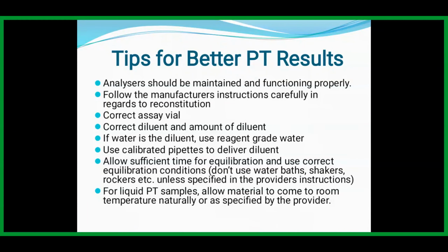If water is the diluent, use reagent grade water. Use calibrated pipettes to deliver diluents, very important. Allow sufficient time for equilibration and use the correct equilibration conditions. Don't use water baths, shakers, rockers, etc., unless specified in the provider's instructions. For liquid PT samples, allow the material to come to room temperature naturally or as specified by the provider.